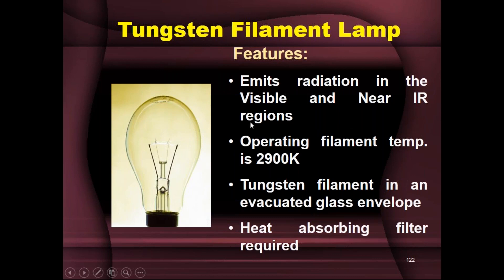The near-IR radiations are not desirable, so to eliminate them we use heat-absorbing filters placed between the source and the next component — the wavelength selector. Even if near-IR radiations are emitted, they are absorbed by this filter and never pass through the wavelength selector, so there's no question of them falling on the sample. This makes the tungsten filament lamp a widely used, reasonably cheap lamp for the visible region.